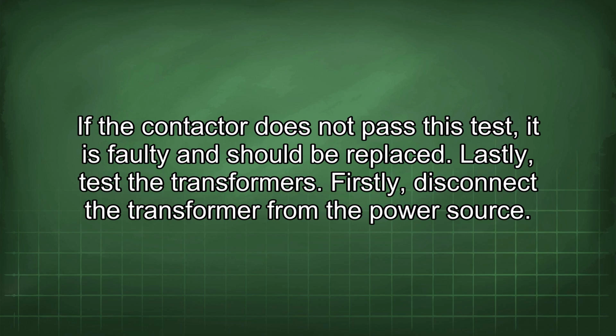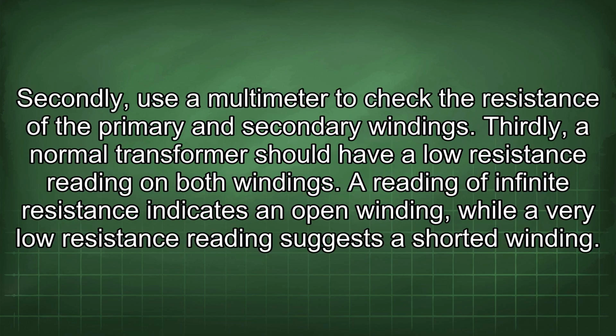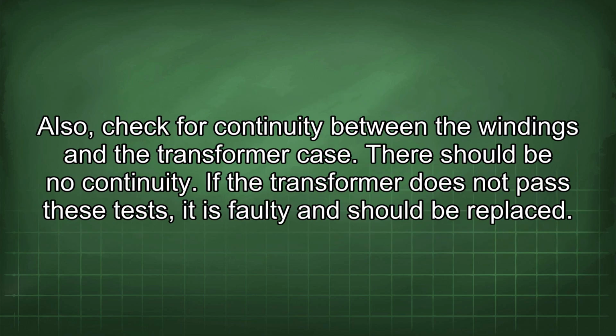Lastly, test the transformers. Firstly, disconnect the transformer from the power source. Secondly, use a multimeter to check the resistance of the primary and secondary windings. Thirdly, a normal transformer should have a low resistance reading on both windings. A reading of infinite resistance indicates an open winding, while a very low resistance reading suggests a shorted winding. Also, check for continuity between the windings and the transformer case. There should be no continuity. If the transformer does not pass these tests, it is faulty and should be replaced.